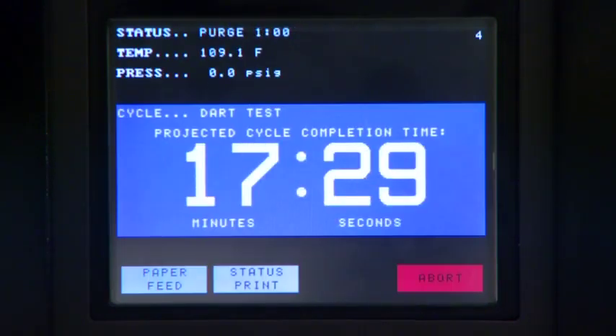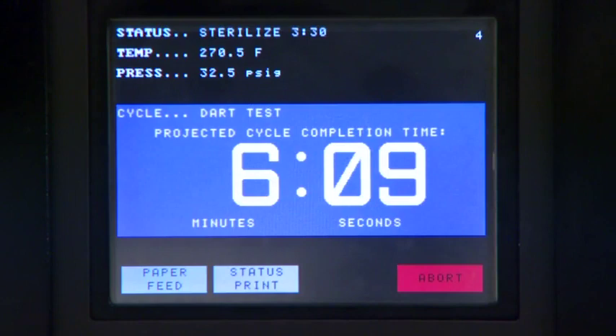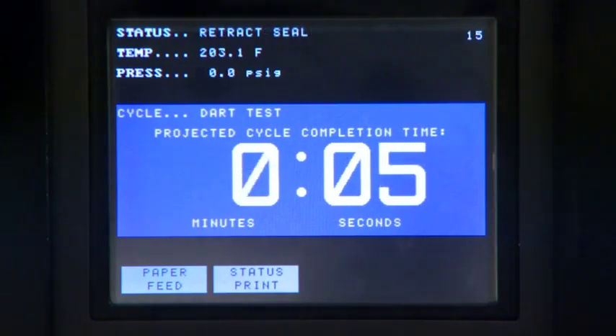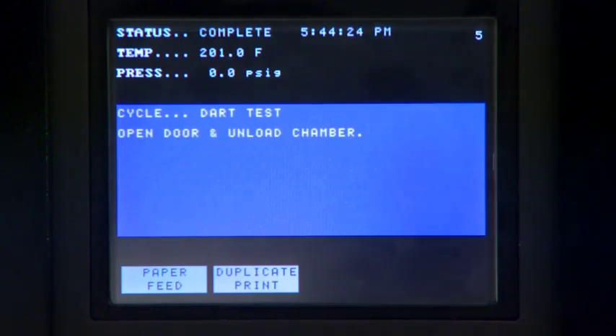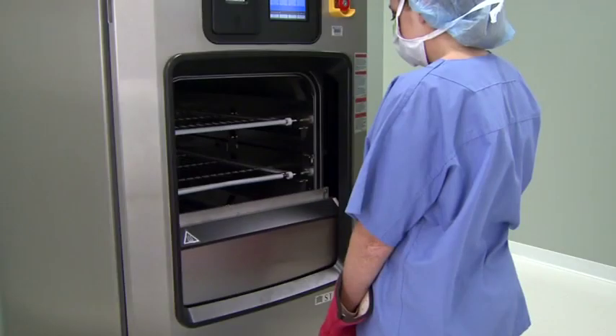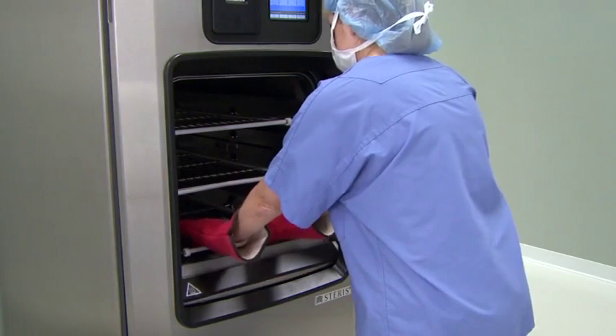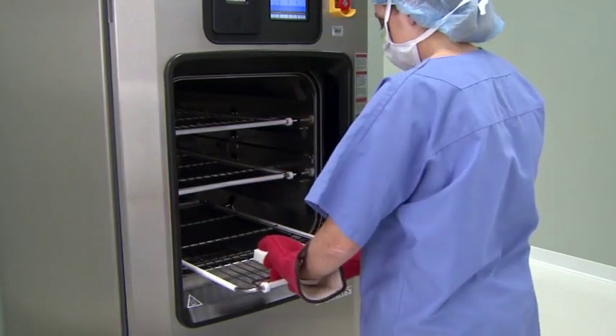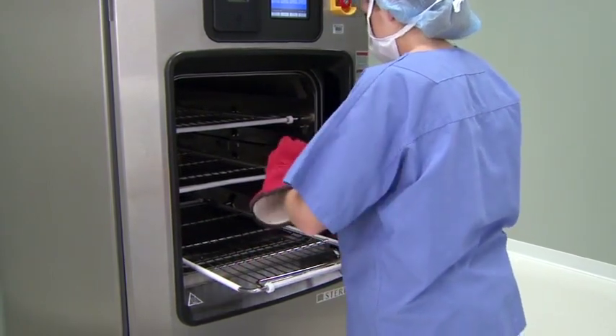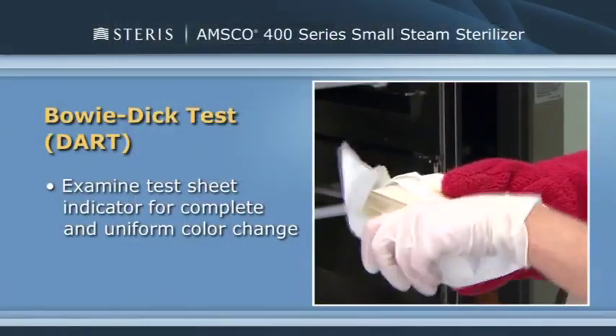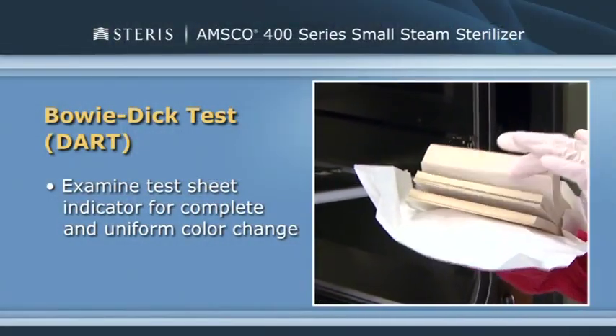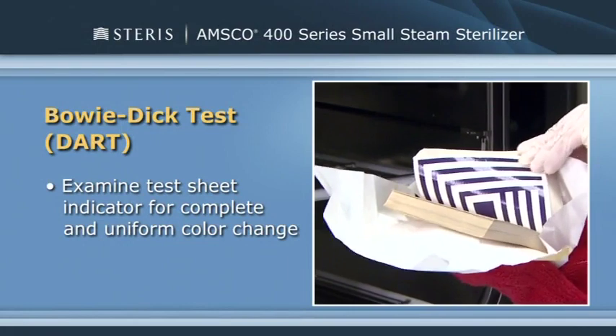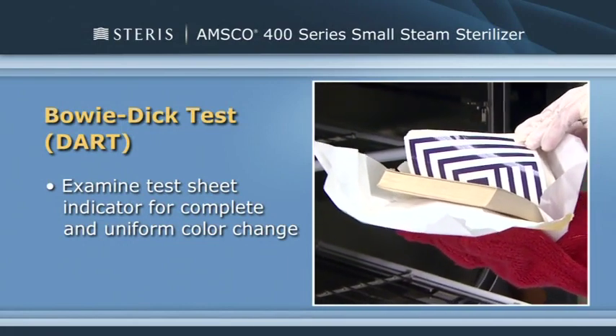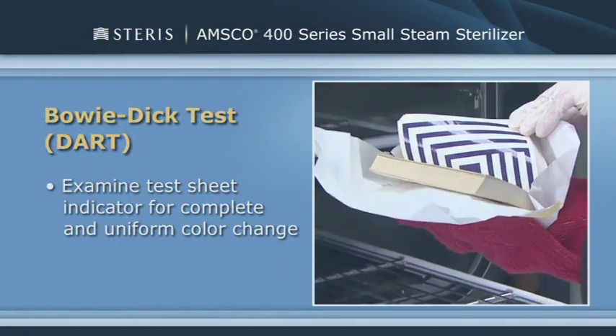The sterilizer temperature will reach 270 degrees Fahrenheit. After 3.5 minutes of sterilize time and 1 minute of dry time, the test cycle is complete. Open the chamber door at the conclusion of the cycle and, wearing your personal protective equipment, carefully remove and open the Dart test or Bowie-Dick test pack. Examine the test sheet indicator for complete and uniform color change. The entire cycle is also documented on the test cycle printout.